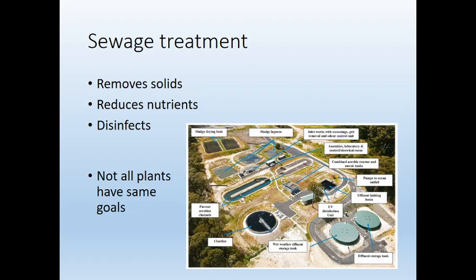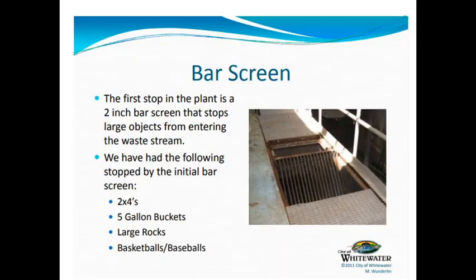I thought the best way to explain this would be to go through how Whitewater's actual sewage treatment plant works. This image is not Whitewater's plant, but it is an example of one. The first thing that happens at Whitewater's sewage plant is there's a bar screen — basically a big grate that stops all the trash. There can be plenty of things that make their way down the drain pipes, and that bar screen stops everything — it's a two-inch bar screen.